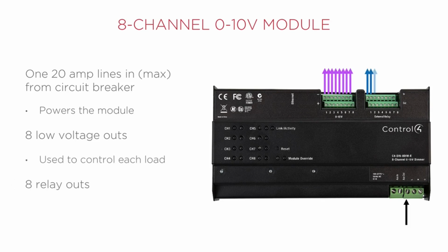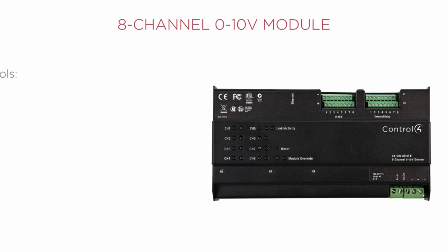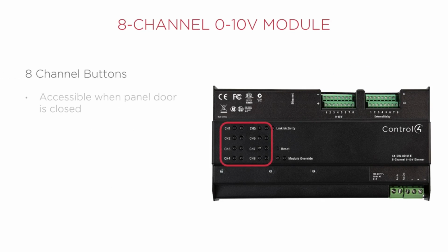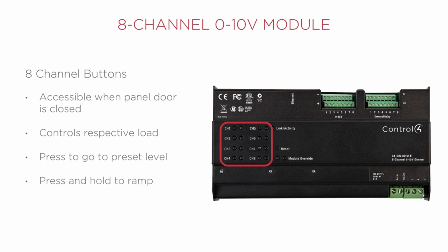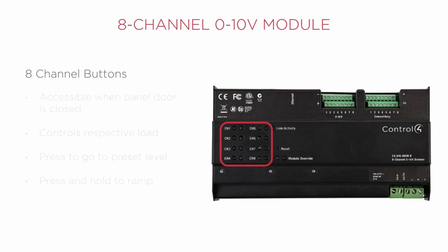8 relay outs are provided if external relays are used to control power for the fixture. The 0 to 10 volt dimmer functions with all protocols: 0 to 10, 1 to 10, 10 to 1, and 10 to 0. The module has 8 channel buttons which are accessible when the panel door is closed, each controlling their respective load. Pressing the button will send the load to the preset level. The button can be pressed and held to ramp that load up and down. And in a fault state, the button can be pressed and held to reset any fault.